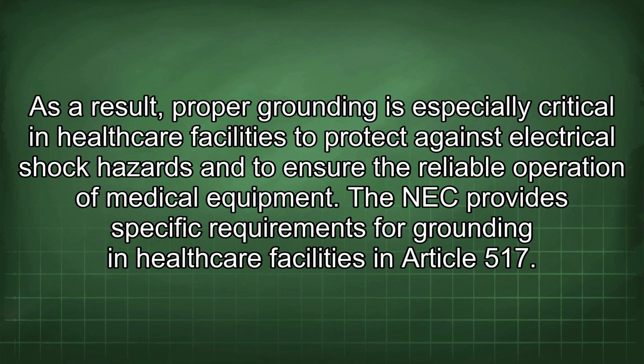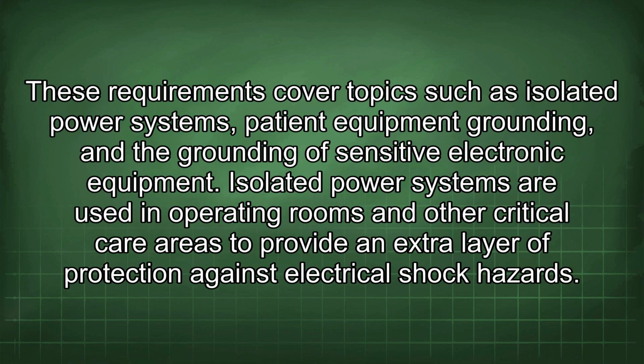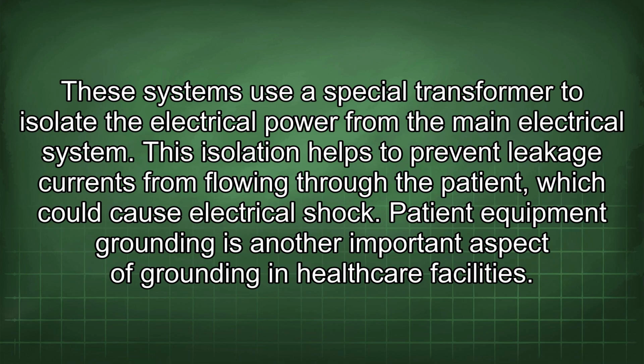The NEC provides specific requirements for grounding in healthcare facilities in Article 517. These requirements cover topics such as isolated power systems, patient equipment grounding, and the grounding of sensitive electronic equipment. Isolated power systems are used in operating rooms and other critical care areas to provide an extra layer of protection against electrical shock hazards. These systems use a special transformer to isolate the electrical power from the main electrical system. This isolation helps to prevent leakage currents from flowing through the patient, which could cause electrical shock.